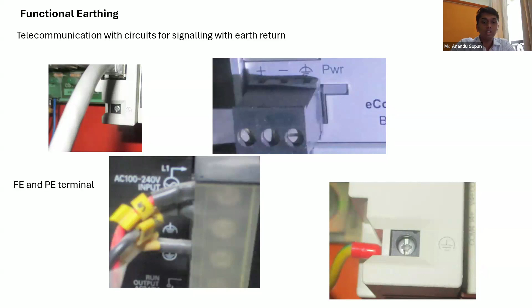Next, coming to our subject, that is our telecommunication buildings with telecommunication equipments. So, what is the requirement for power distribution and for protection against shock? What are the general requirements? The best system you can go for is the TNS system. You have your separate metallic fault return path from your equipment to the source. And in case you are using a TNC distributed supply, at the commencement of supply, you have to change it to TNS. So it will be kind of like a TNCS.